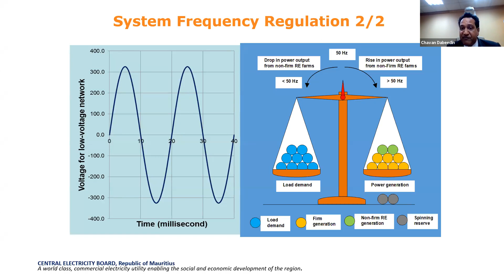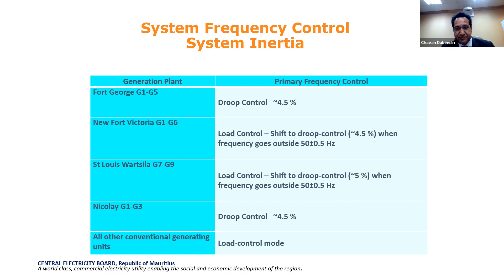Our power stations in Mauritius, CEB's power stations, work on droop control mode. So whenever there is a fluctuation in frequency, the output of these power stations will go up and down to correct the frequency. For example, if the frequency tends to be lower, these power stations will push more power to bring the frequency to 50 hertz. Whereas the IPPs are set on load control mode, which means that they only push fixed power. There are fewer changes in output. Whereas CEB, the utility power stations, tend to go up and down to correct frequency. They not only give supply, but they also need to correct the frequency.